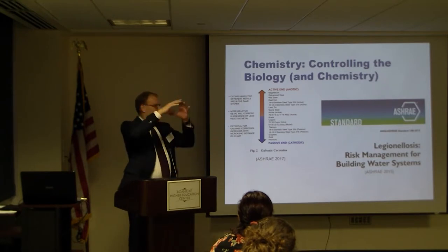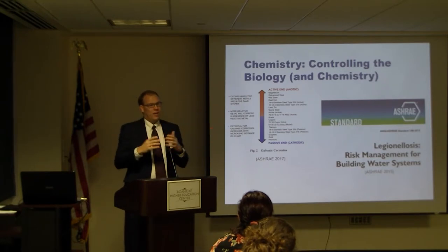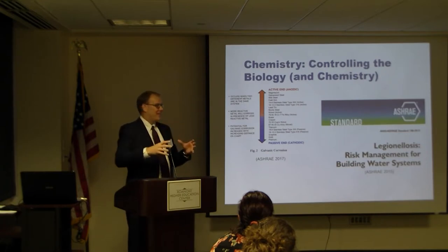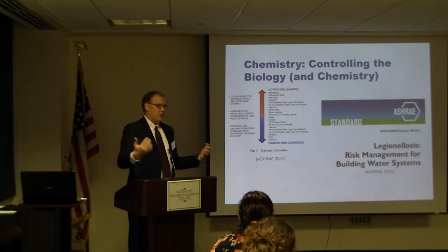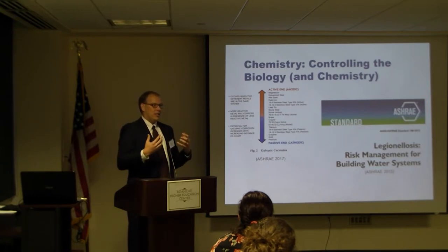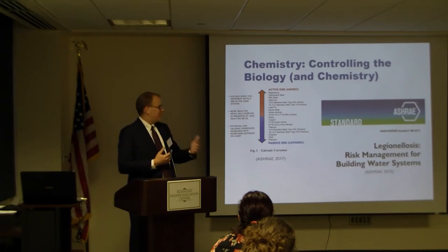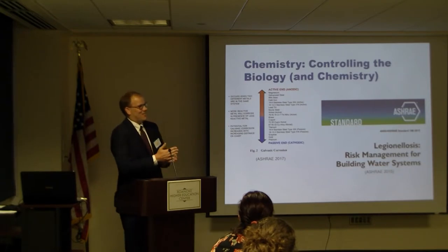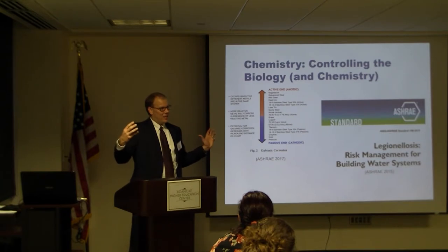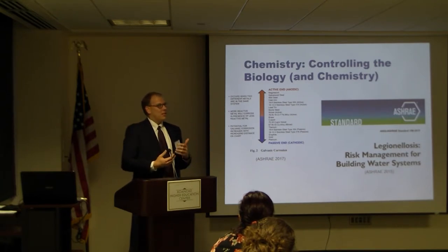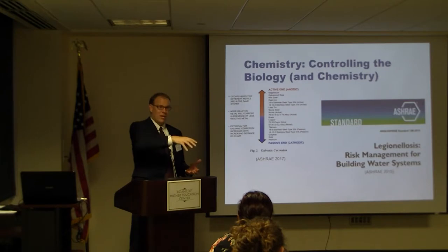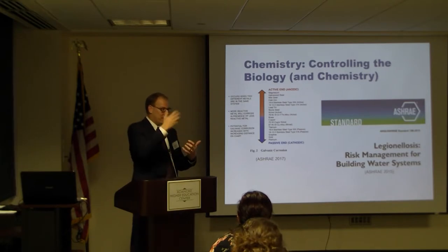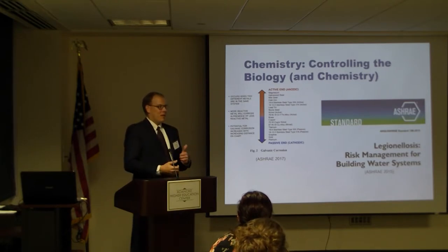What happens at the cooling tower? We run it through shower heads, and we spray it over, fancy term we call fill, but essentially just a bunch of plastic, and we run a fan at the top of it. And we let the air come across all that plastic fill, across all that shower-driven air, and because of the wet bulb temperature and humidity level in there, typically that is a lot cooler than 85 degrees. So all of a sudden, we're sending 95 degree water out of the shower head over the plastic fill, drawing some cooler air across it, and cooling all that water back down. A lot of good things for that.